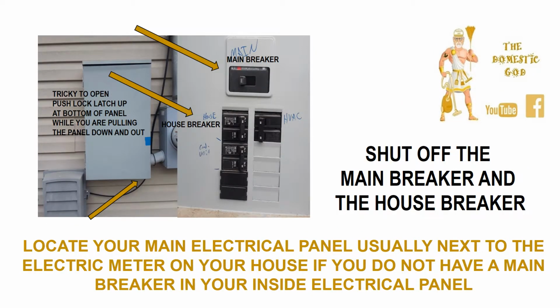When you go outside to locate your main electrical panel, it's usually next to the electric meter on your house if you do not have a main breaker in your inside electrical panel. Remember to shut off the main breaker and the house breaker. When you look at the electrical panel box outside, it's going to be rectangular and usually gray next to the electric meter. It's kind of tricky to open. You need to push the latch up at the bottom and pull the panel door down and out at the same time.